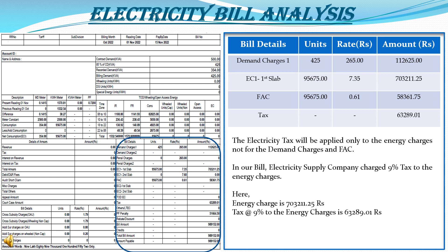The tax section: electricity tax is applied only to the energy charges, not to the demand charges and fuel adjustment cost. In our bill, the energy charges are 7,03,211.25 rupees. In our state, the electricity tax is 9%, so 9% of 7,02,211.25 equals 63,289 rupees, which is mentioned in the electricity bill.